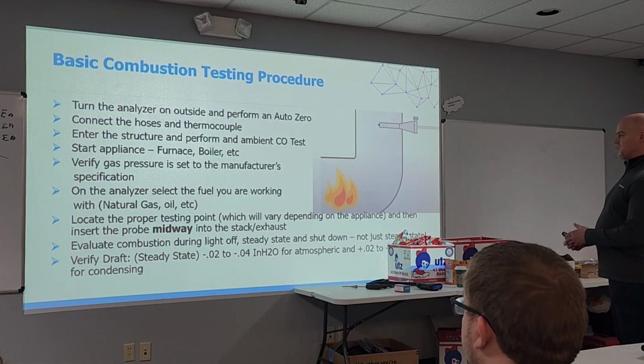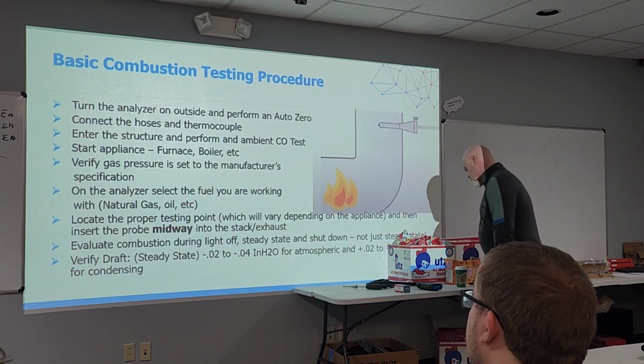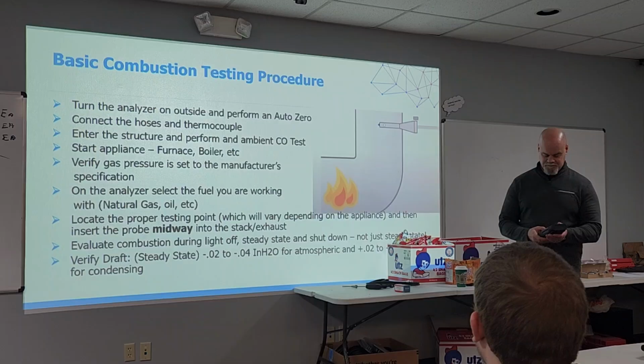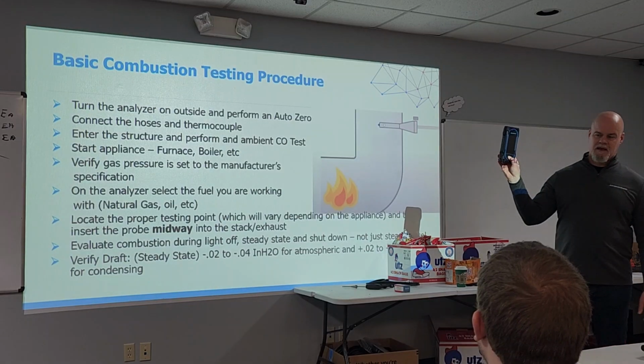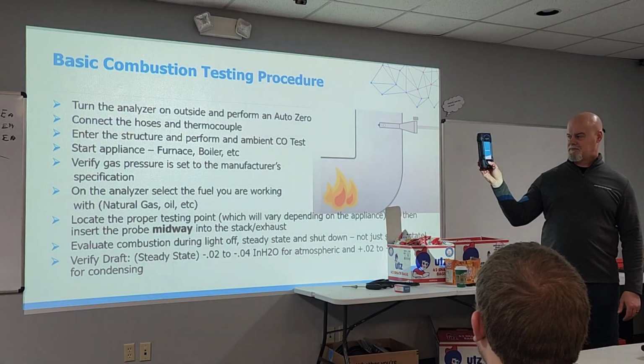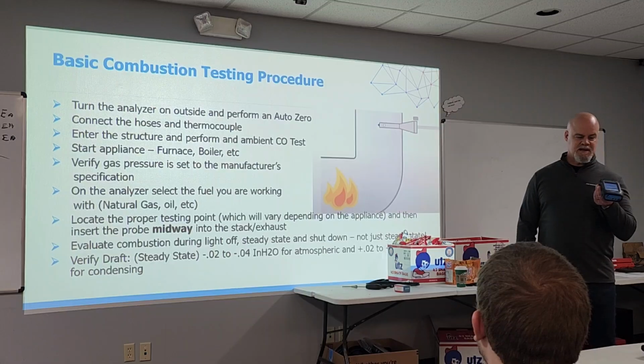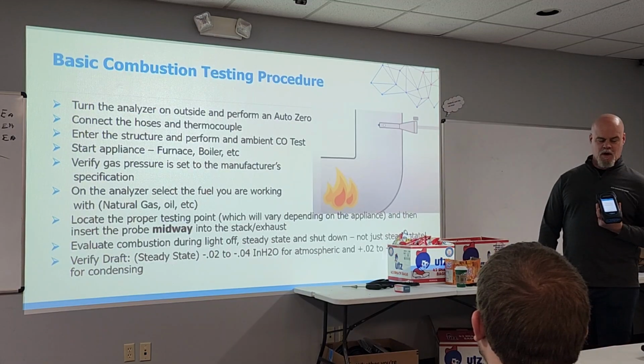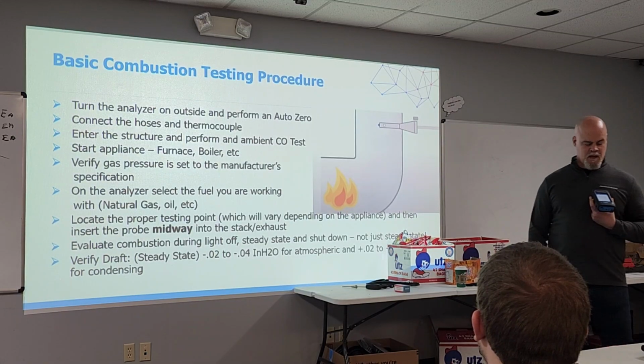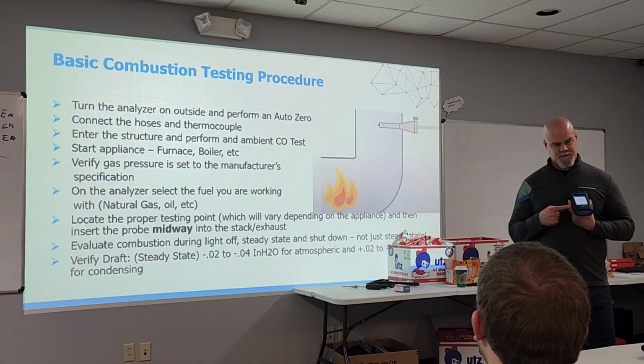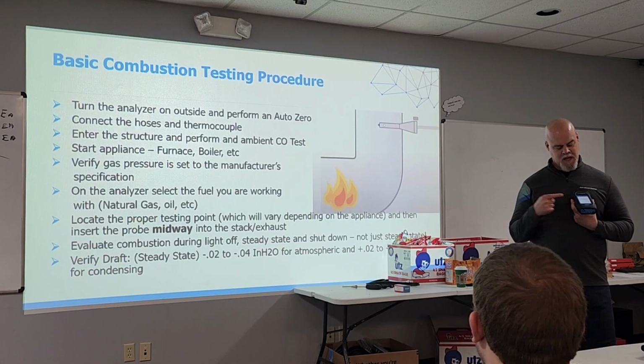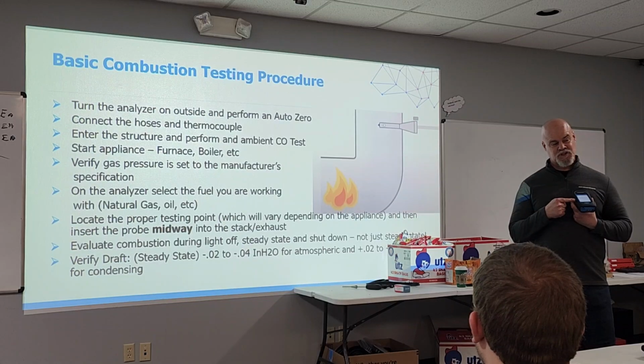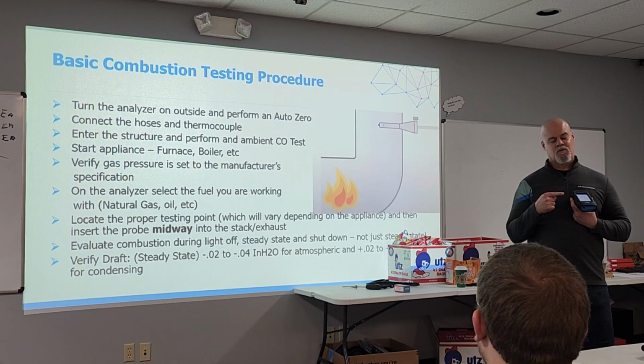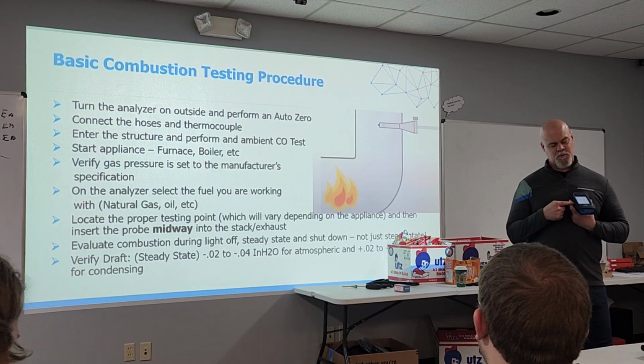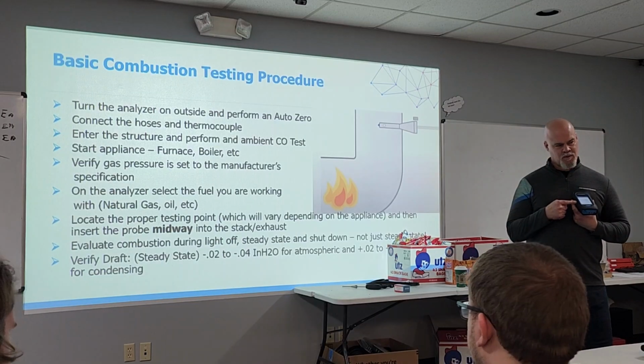So, basic testing procedure: turn this on outside, in fresh air, with no probes or hoses attached. If you turned it on inside instead, and there was 100 ppm of CO in the room, it would negate it, because on startup it gives you 20.9% oxygen, 0 CO, and 0.06% CO2.